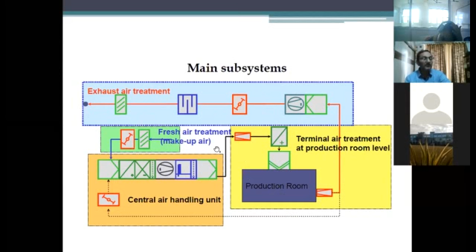Air cannot be recirculated. So in such cases, this type of system will be there, where fresh air is coming inside. There are louvers over there. This is the air valve to control the amount of air coming inside. There's a blower, you have the filters, then the cooling coil, then the humidity control or the vapor generator or the vapor removal, and then the pre-filter, final filter over here, and then HEPA filter over here. And this is the regulator of the amount of air which is going inside. Right? So this is how this unit operates. When 100% exhaust is there, there is no recirculation of air.